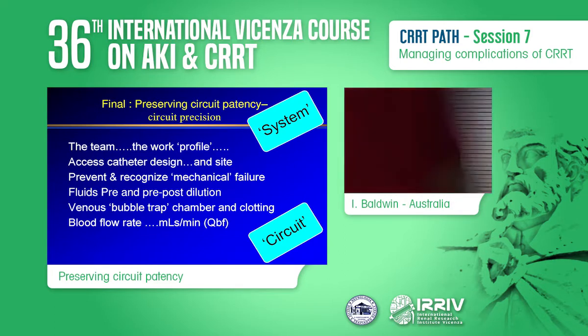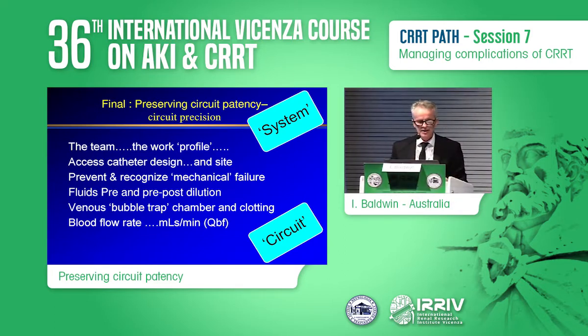So I think my last slide, thank you, Madam and Mr. Chair. I'll just leave you with these points. The team's really important, our access catheters. We need to recognise mechanical failure and differentiate that from anticoagulant therapy. Pre and post fluids, our bubble trap design and our blood flow rate are really important. So a little speedy finish, but I say thank you very much.